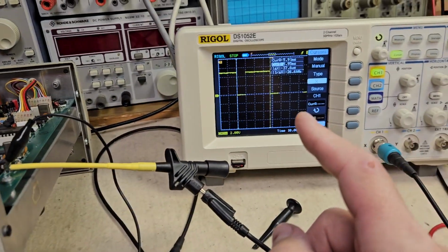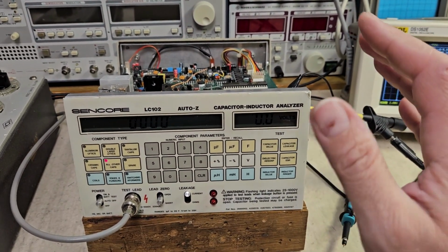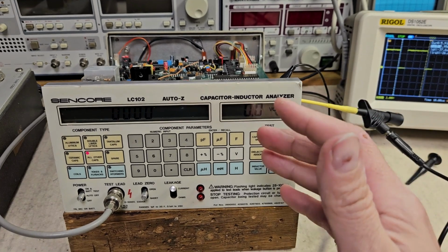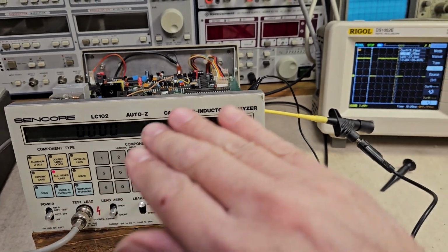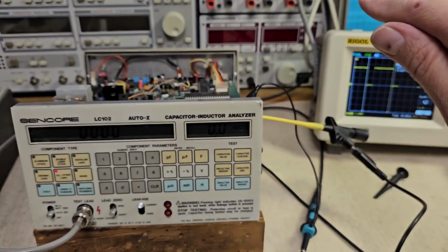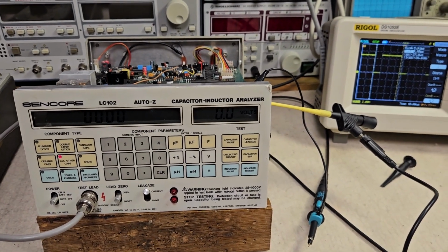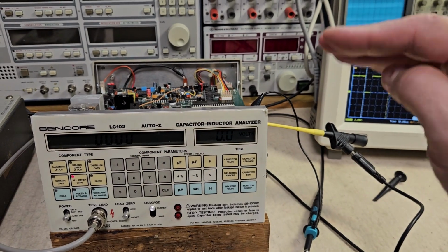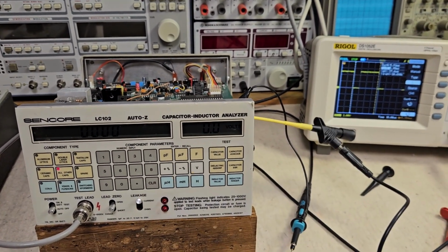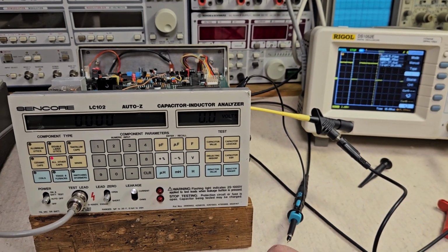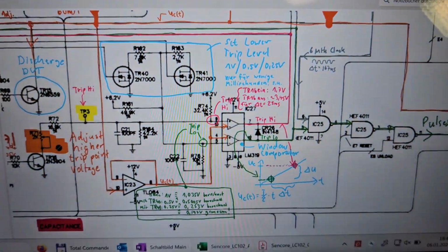I made measurements. It's quite tricky, the technique behind how they determine the value. They use a current source, which causes a linear rise of the voltage in the capacitor to be tested, and then you have two voltage values between which you count pulses. I made my own notes here.